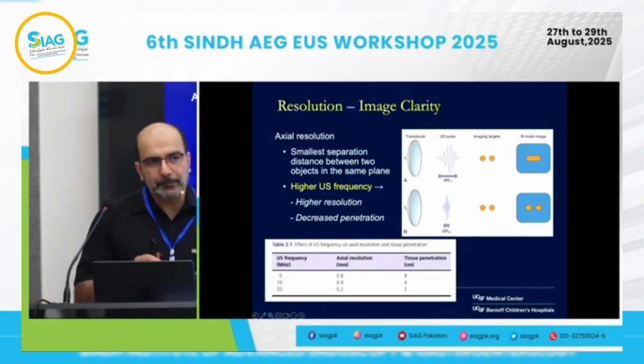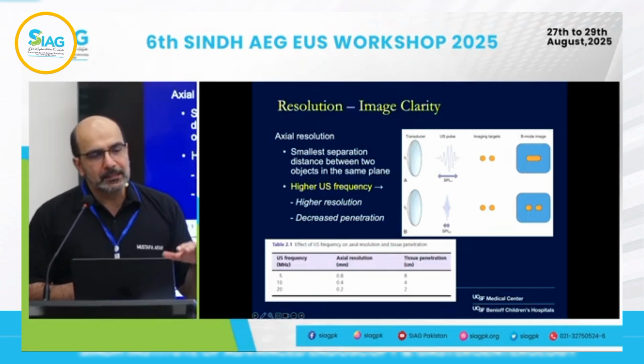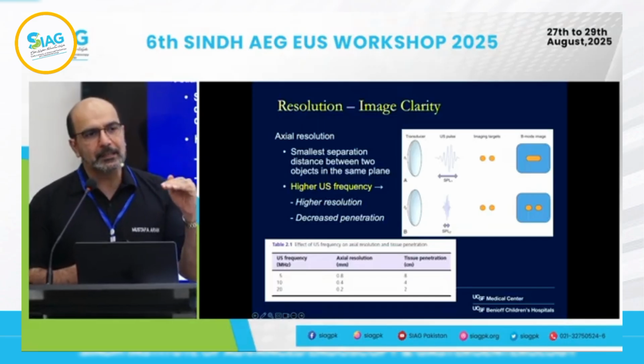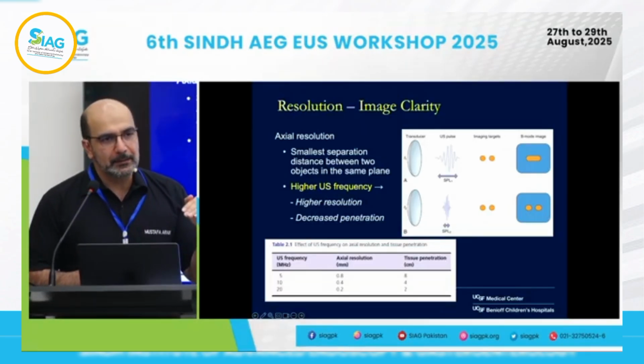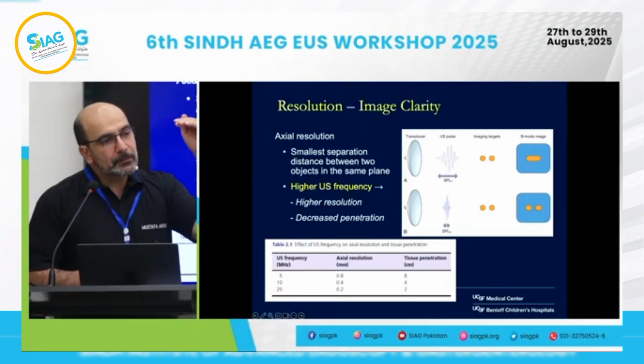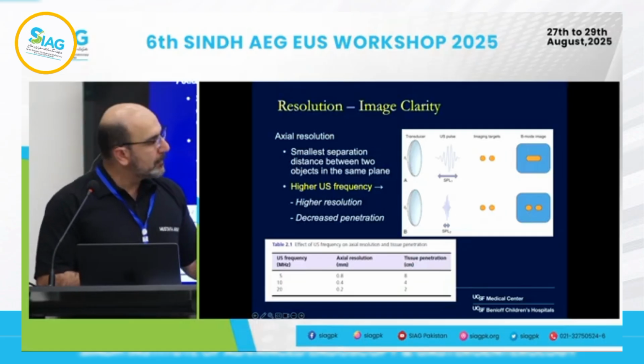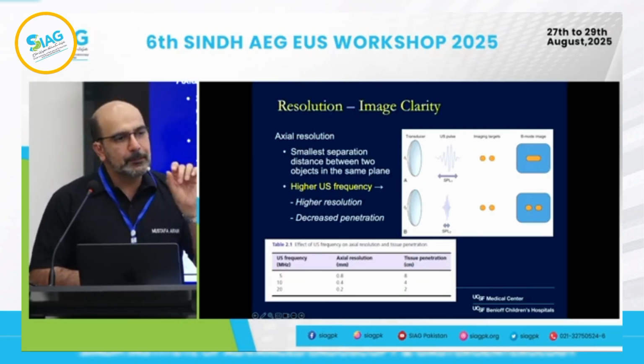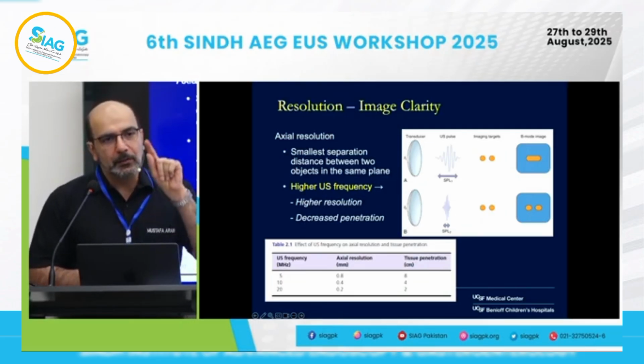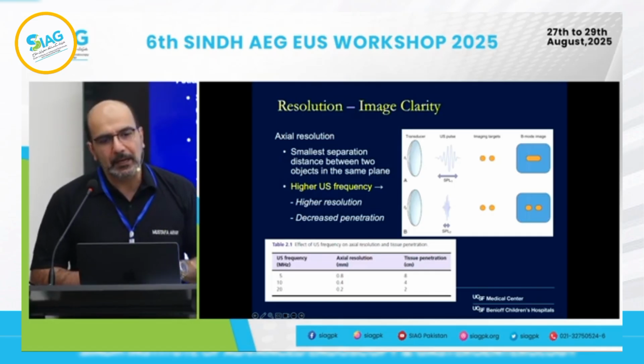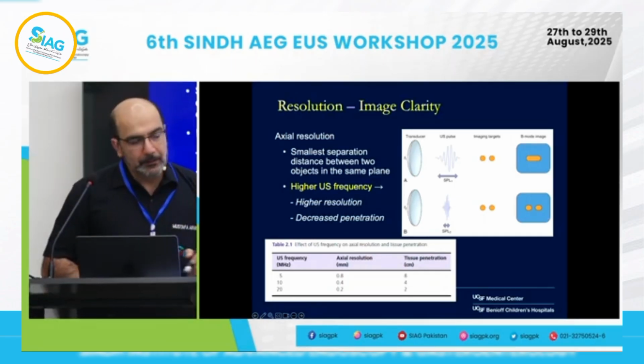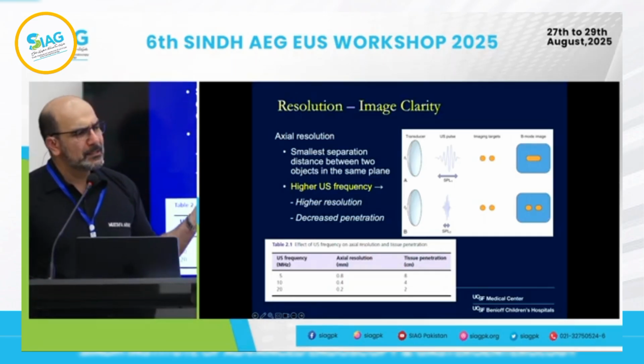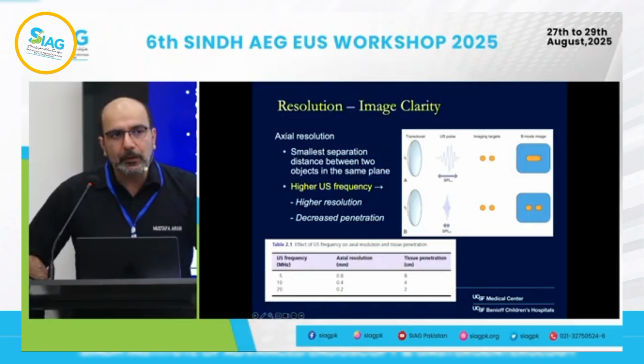Just for basic principles, most EUS is done at 7; the default setting is 7.5 megahertz. You can go up to 10, but for anything higher, you have to have mini probes. They're small probes that go much faster, and they can give you higher frequency. We don't use those very much, but you need to at least be aware of these principles.